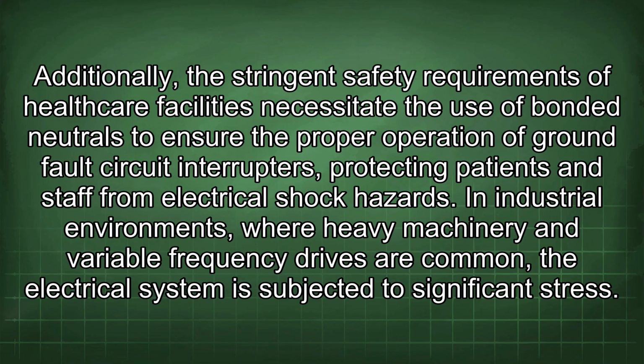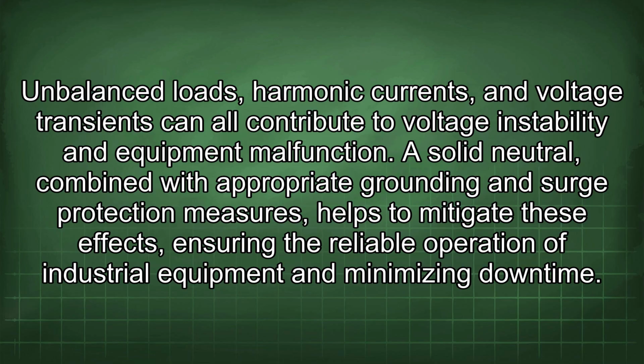In industrial environments, where heavy machinery and variable frequency drives are common, the electrical system is subjected to significant stress. Unbalanced loads, harmonic currents, and voltage transients can all contribute to voltage instability and equipment malfunction. A solid neutral, combined with appropriate grounding and surge protection measures, helps to mitigate these effects, ensuring the reliable operation of industrial equipment and minimizing downtime.